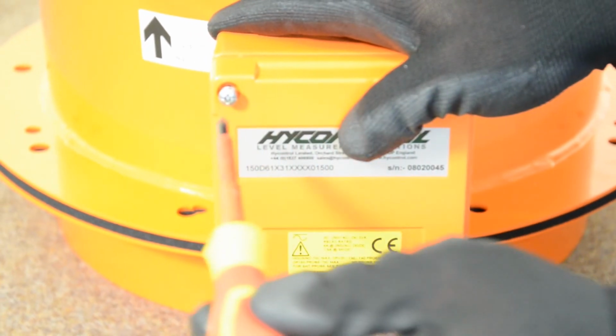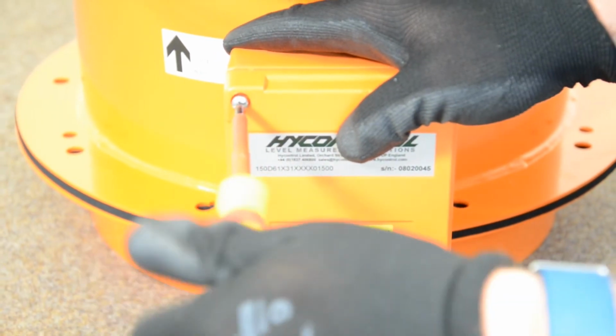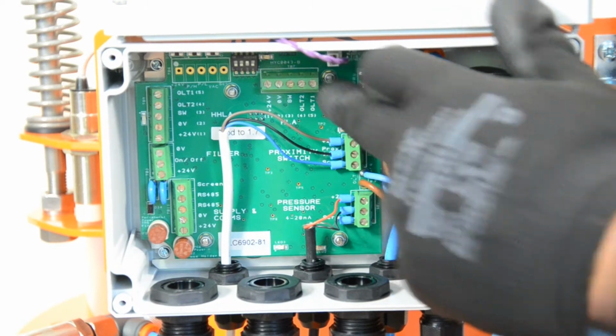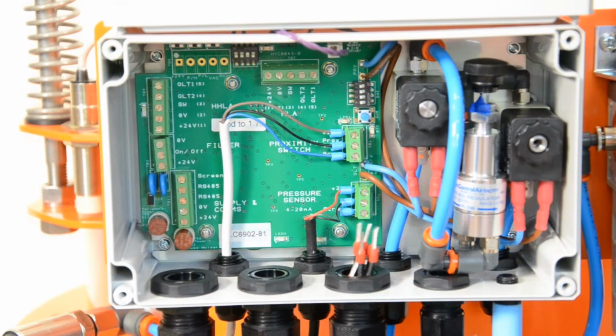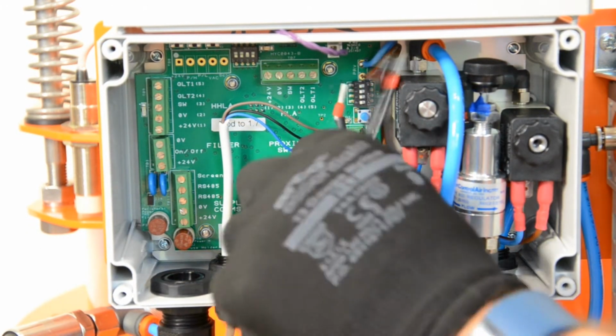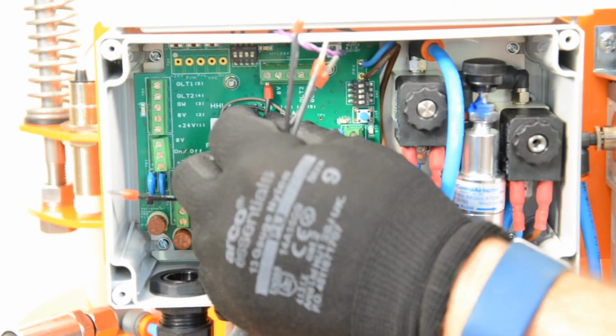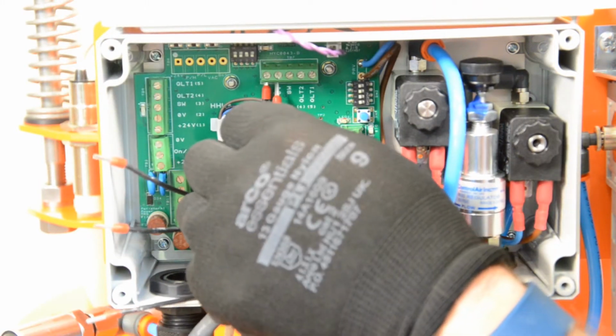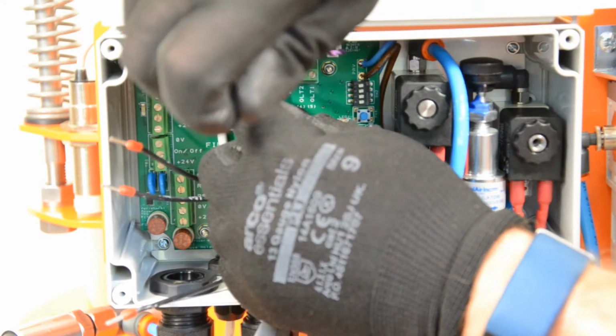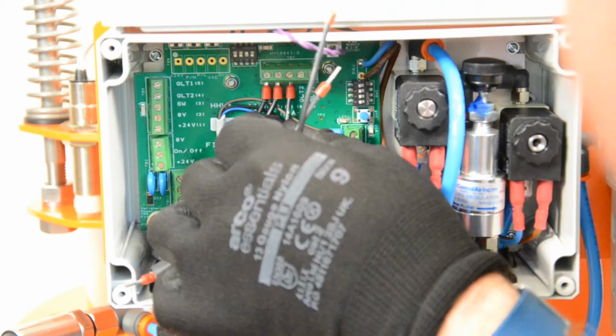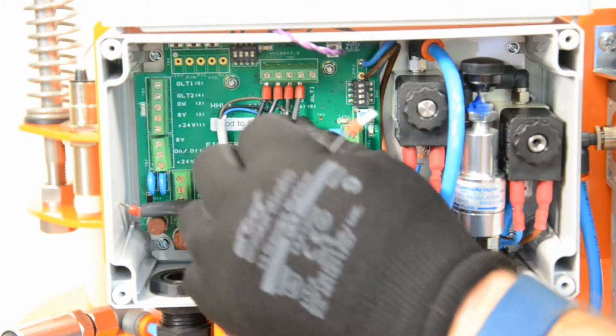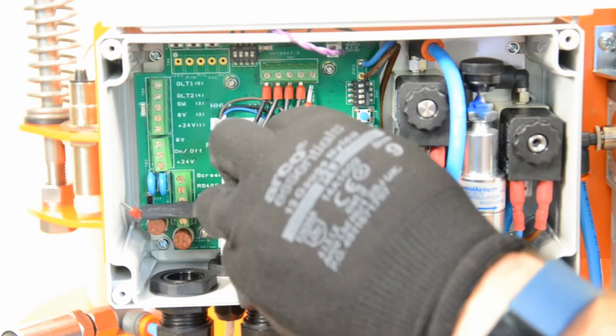Put the cover back on and move on to the PRV control box. The level probe will be wired to TB7. Insert the 5-core cable through the third grommet. Note that the correct wiring sequence is visible on the PCB. Follow this to wire the probe correctly. Cable 1 to terminal 1, 2 to 2, 3 to 3, 4 to 4, and 5 to 5.